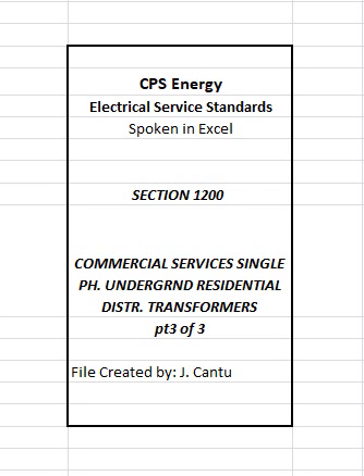1205 Secondary and Service Lateral. Secondary and service lateral exiting the transformer and/or secondary enclosure shall be totally enclosed in conduit. The conduits shall be continuous except for watertight coupling. All conduits, elbows, and couplings shall be furnished by customer as required below. 1205.1 Customer's property. Customer shall furnish, install, and maintain the service conduits and conductors between the single-phase transformer or secondary enclosure and customer's service equipment. CPS Energy shall make all connections to transformer secondary terminals or in secondary enclosures.